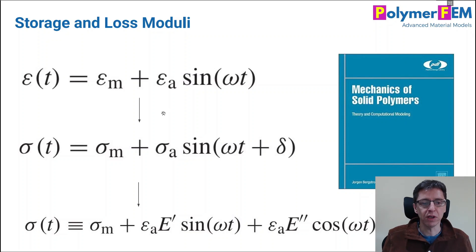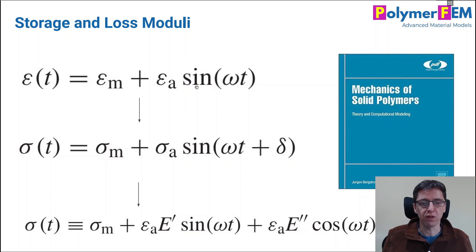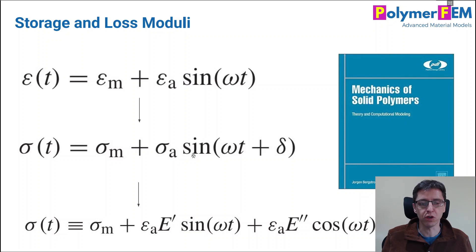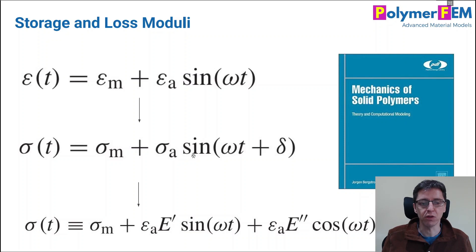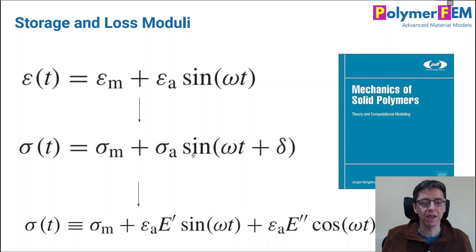But we can see one assumption really here right away: there are of course materials where the stress response is not sinusoidal when the strain response is sinusoidal. This would be non-linear viscoelastic or viscoplastic materials where the output response may be different. In those cases, a dynamic test where you get storage and loss modulus may be of lesser value unless you know exactly how the software that was used to extract the storage and loss modulus worked. For non-linear viscoplastic materials, it's typically better to work in the time domain instead of storage and loss modulus.